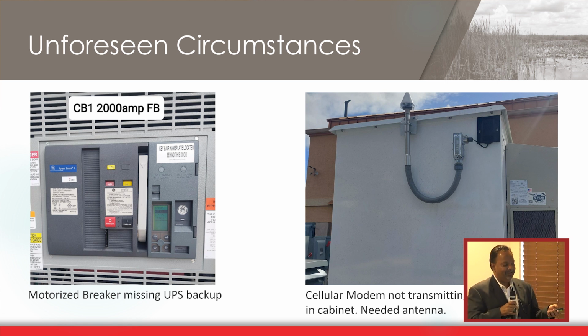So that's why we had to install a UPS to back up the motorized breaker in order to make it function. It took about a month for us, or the contractor, to figure that out, and they had to report back to the supplier, who had to redesign their motorized breakers to facilitate that.